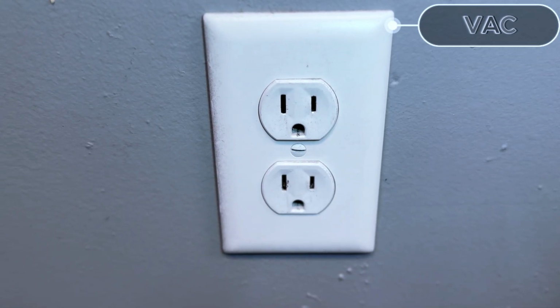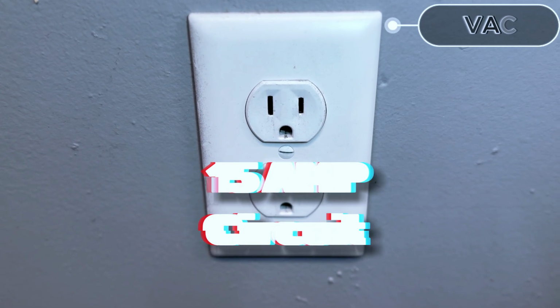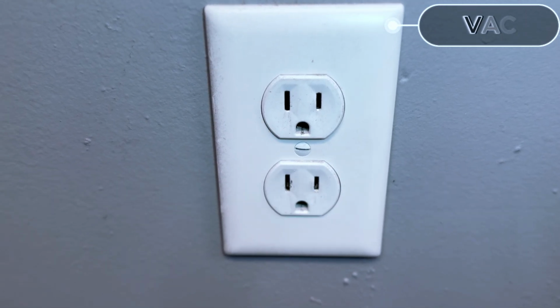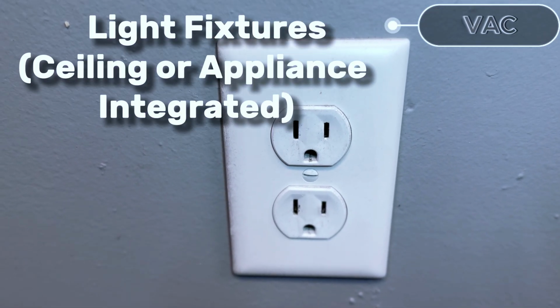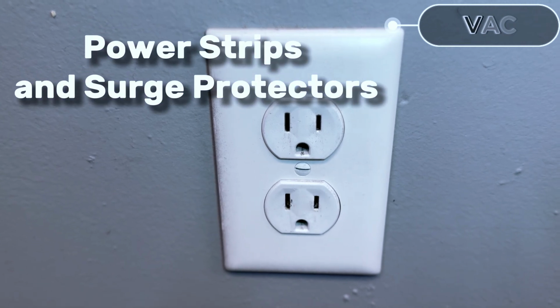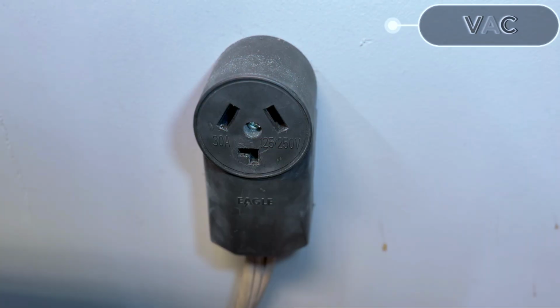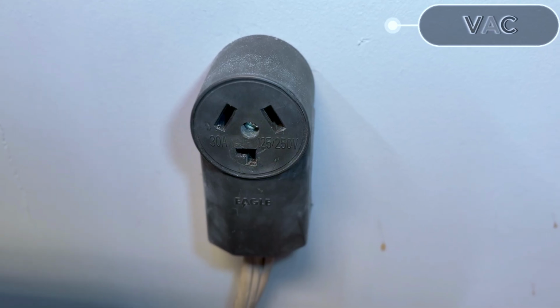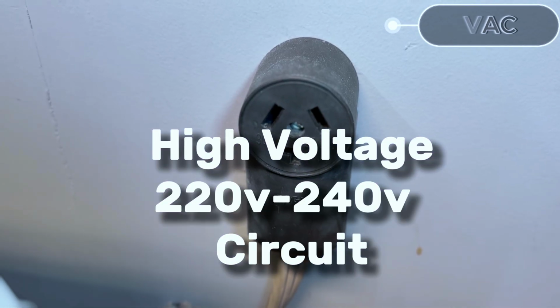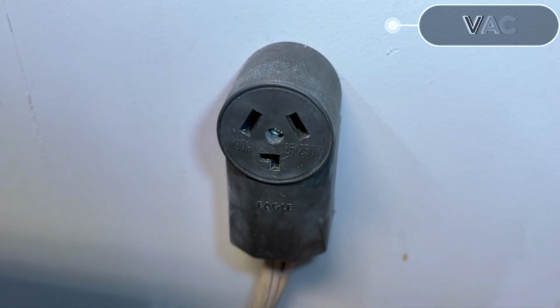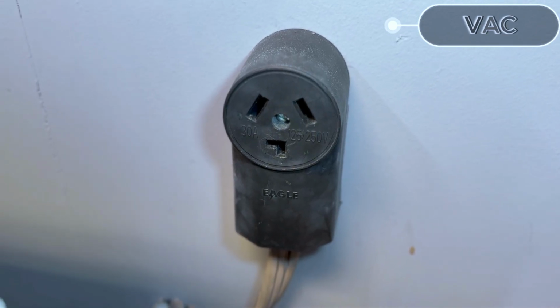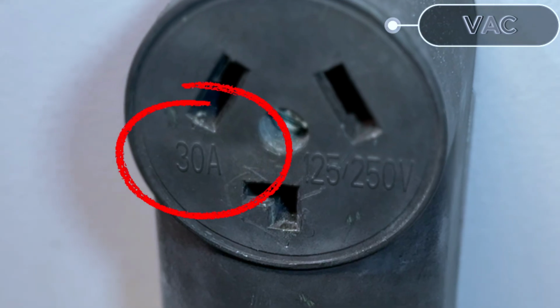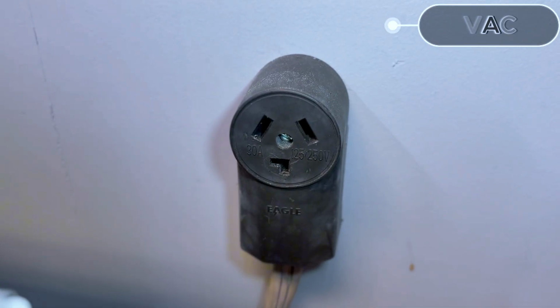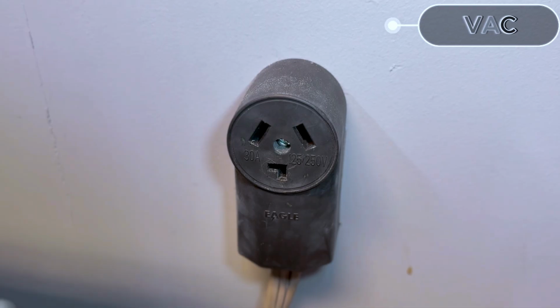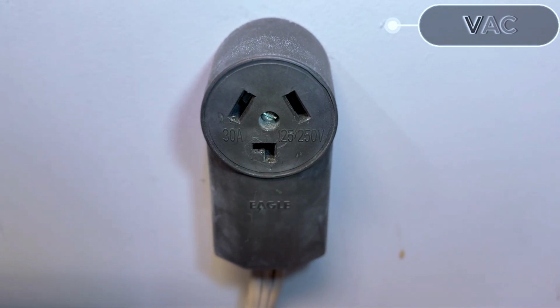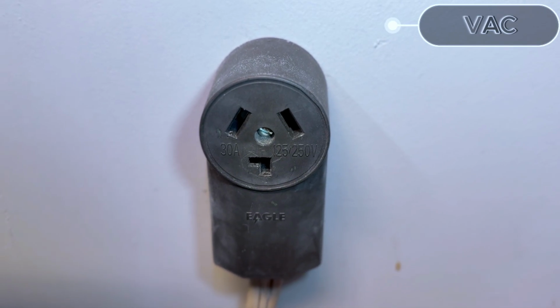Here's another example where you can find AC voltage, and this is just a standard regular outlet. As you can see, it looks a little bit different than the 20 amp circuit. This should be on a 15 amp circuit, and this is a standard outlet. You can also find AC voltage on larger outlets like these. These are designed for 220 to 240 volt. Usually you'll find these on 30 to 40 amp circuits. As you can see, this one's marked for a 30 amp. Now, these larger 220, 240 volt outlets can come in 3-prong or 4-prong. These outlets are designed for larger appliances like dryers, ranges, and so forth.